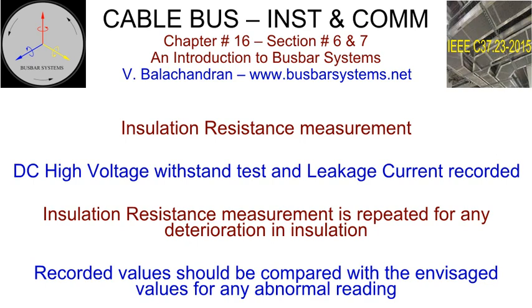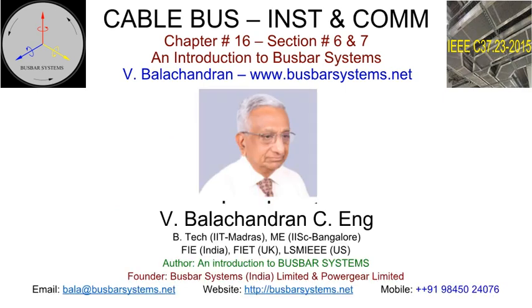Recommended value of DC voltage to be applied for 1 minute and leakage current recorded. Insulation measurement test to be repeated to check any deterioration in insulation after conducting the high voltage test. The recorded values should be compared with the envisaged values for any abnormal reading. The terminating ends are to be connected and all inspection openings of the adapter box to be closed at all terminating ends.